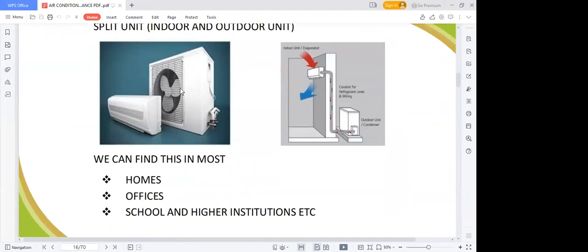You see, they separate the indoor and the outdoor unit. You can see the way they have installed it. The outdoor unit is here. Please, at no time should you install your outdoor unit too close to the wall. You must give enough space behind it. The essence of the space is for it to suck air to cool the compressor. If you install it too close to the wall, you are damaging your compressor.